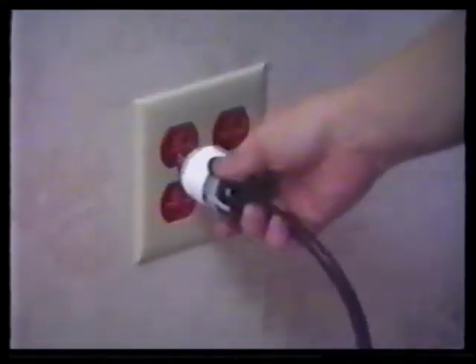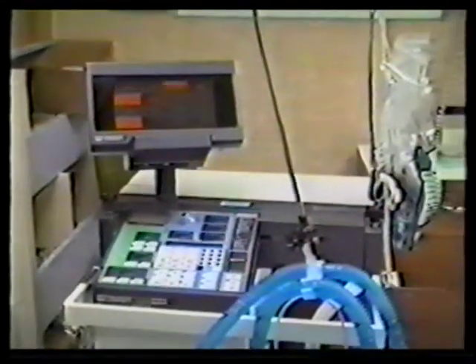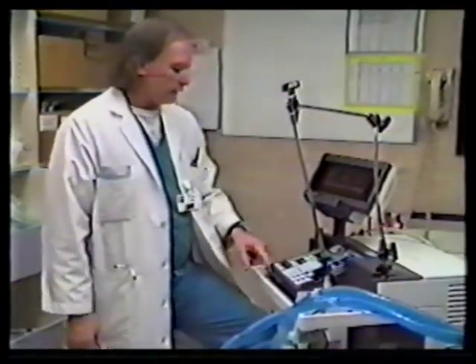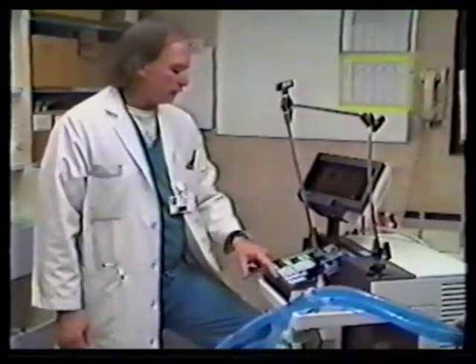it could be internally. If you have an electrical outage, the hospital does have red outlets throughout the hospital that are on emergency power generators, which will come on and be active within 10 seconds of the power outage. All critical care type patient equipment should always be plugged into the red outlets. If the power goes out and there is a hesitation when the power returns, all the equipment should be checked to make sure that it returned to the settings that it originally was set at.